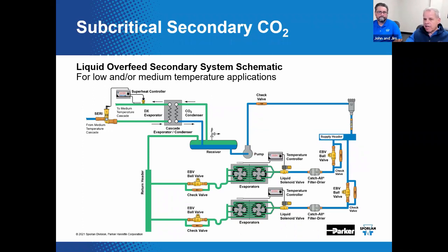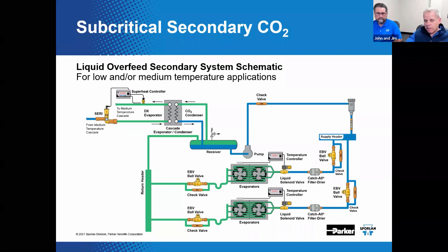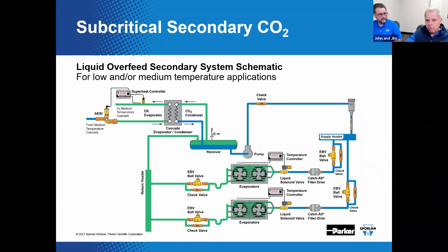Yep. The liquid is fed from the pump to the display cases with filtration to remove moisture and contaminants. What an idea that would be. We can see some catch-alls being deployed here. The temperature inside of the display cases is controlled by cycling a liquid line solenoid valve and a temperature controller. As heat is transferred in the evaporator of the case, CO2 evaporates to a liquid vapor mix and ultimately returns to the receiver. Note, we've got a check valve piped in parallel with the ball valve for safety. Most ball valves will require this to ensure liquid CO2 cannot become trapped during service, except if you use that fancy ball valve check combination that we make.